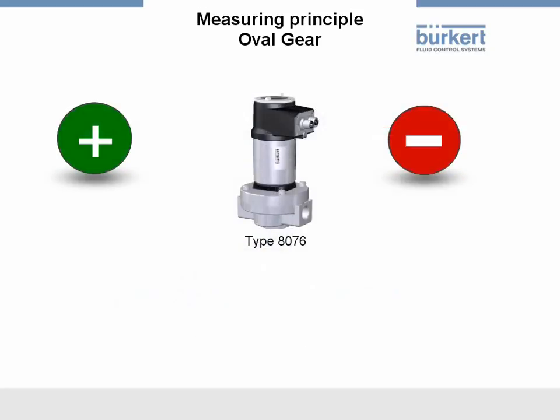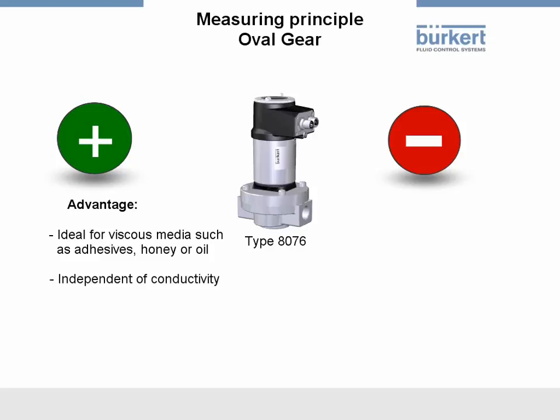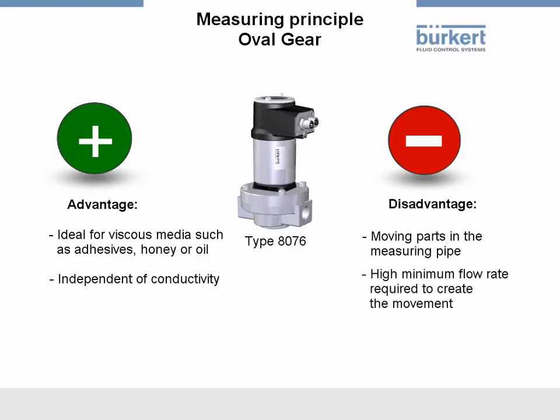Flow measurement with oval gears is ideal for viscous media such as adhesives, honey, or oil. The measurement is not dependent on the conductivity. The disadvantages of this measuring method are the moving parts in the measuring pipe, the high minimum flow rate required to create the movement, and the very high pressure drop.